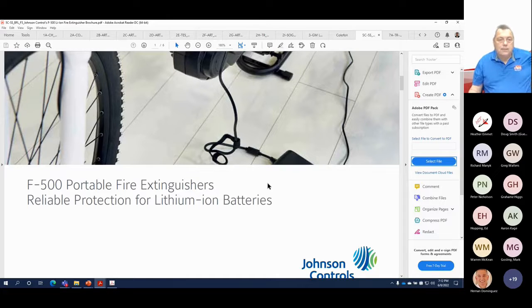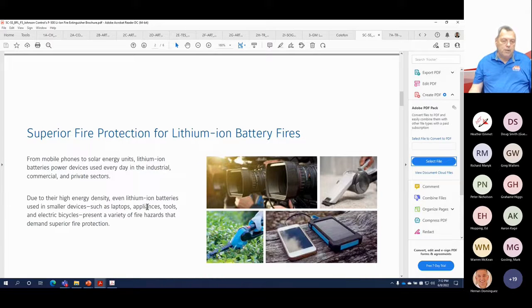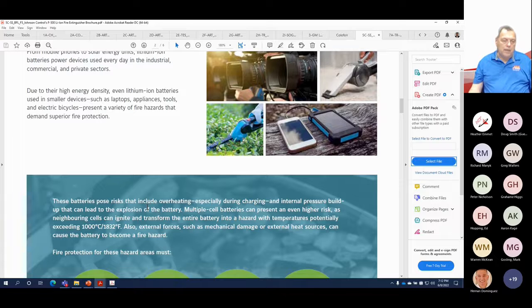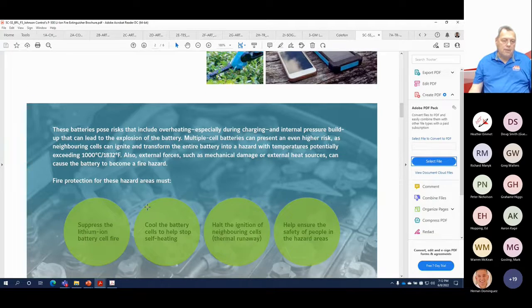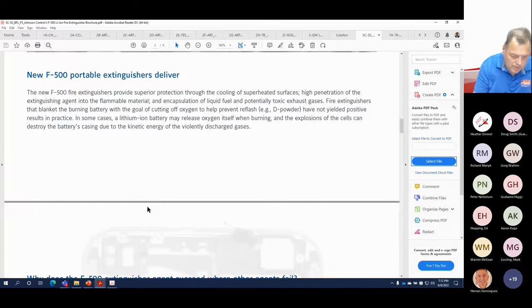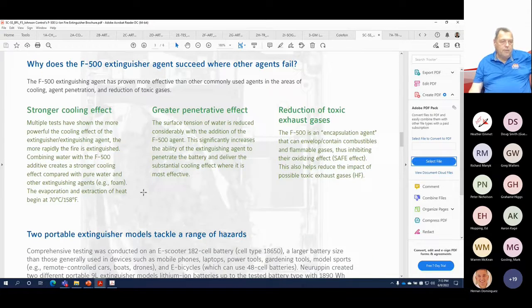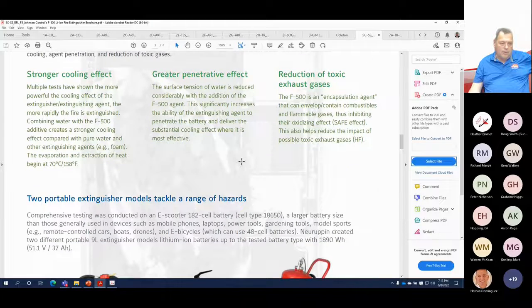To me, this document we're looking at is probably the single best endorsement of F500 for lithium-ion battery. Why? Because Johnson Controls is the largest foam manufacturer in the world, the largest dry powder fire extinguisher supplier in the world. They supply FM200, they supply Novec, and yet this is what they're pressing to their customers as the solution for lithium-ion battery. They mention stronger cooling, effective penetration, reduction of toxic exhaust gas, much safer.